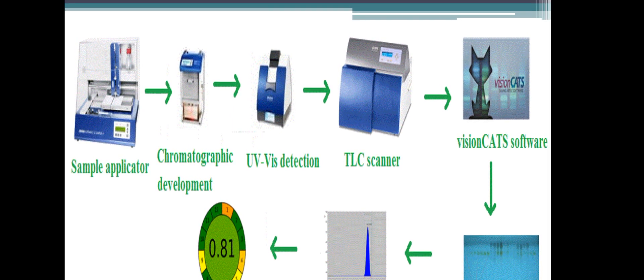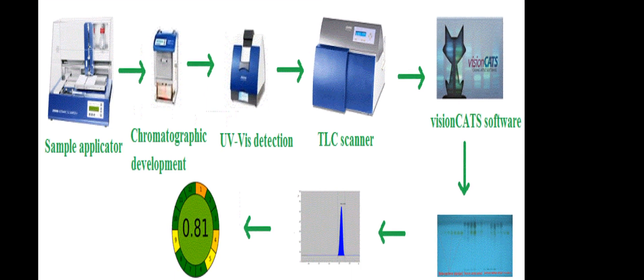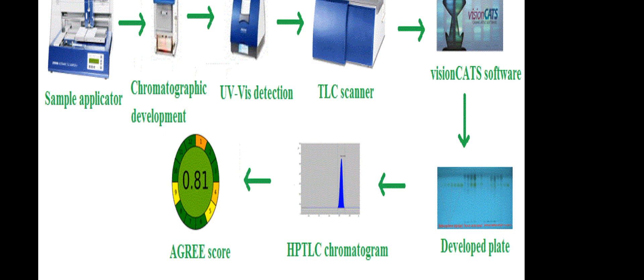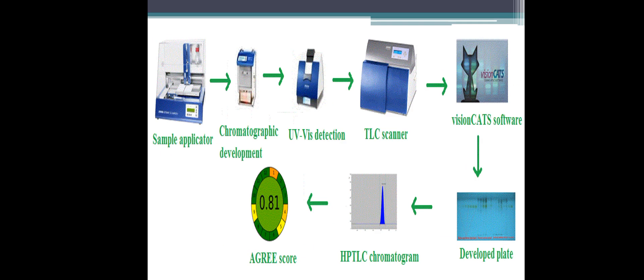This is the general diagram for the working of HPTLC. First, a sample applicator is used in which the sample is applied over the precoated plates. After that, chromatographic development takes place, followed by UV-visible detection in which the sample is detected and its RF values are recorded. A TLC scanner then scans the components on the plate, and visionCATS software detects the components. The developed plate shows the HPTLC chromatogram and the score.